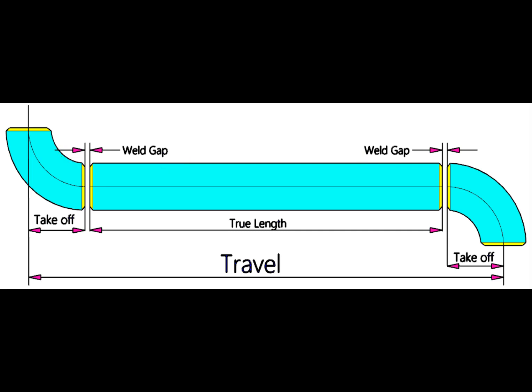So how we will calculate the true length of the spool? The true length or cut length is: add 2 welding gaps and 2 take offs, then minus this sum from the travel.